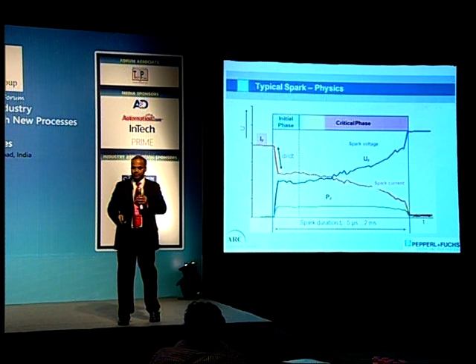In intrinsically safe design, we limit the voltage and the current to a very low value. The power is kept to an extremely small level, and even if the cable breaks, it's not going to create a problem.